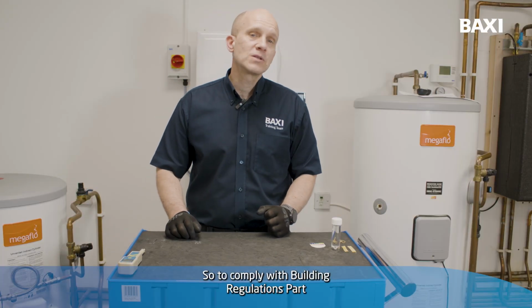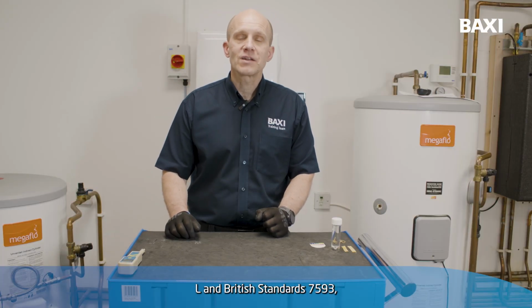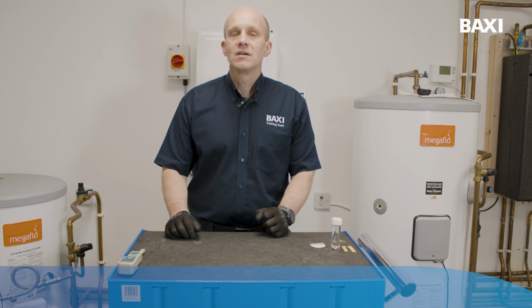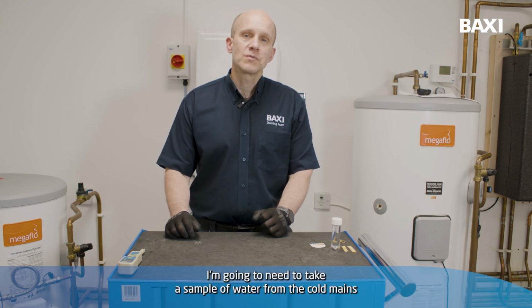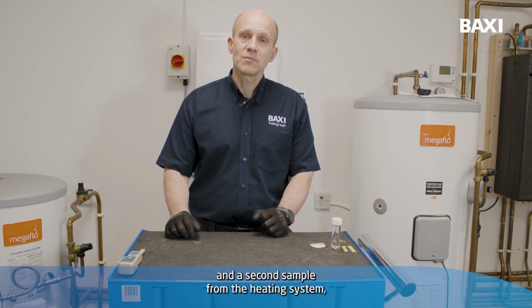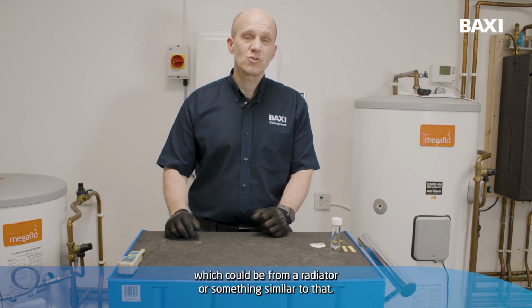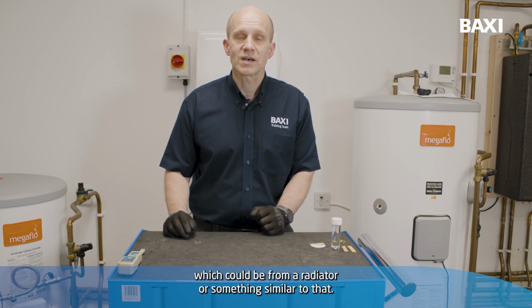So to comply with building regulations Part L and British Standard 7593, I'm going to need to take a sample of water from the cold mains and a second sample from the heating system, which could be from a radiator or something similar to that.